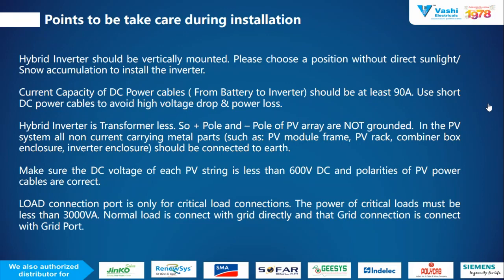Next thing is the polarity of the PV string should be correct. Means you have to check the polarity of the PV string as well as the battery. For the battery connection, you have to check the voltage with a multimeter, and only then connect it to the hybrid inverter. Also, the critical load should be less than or equal to 3000 VA. This is a major thing we have to take care of during installation. Means your critical load must be limited to less than or equal to 3000 VA. Next.